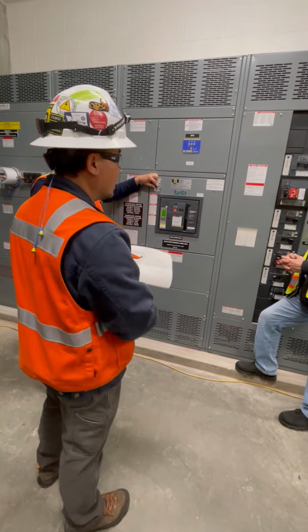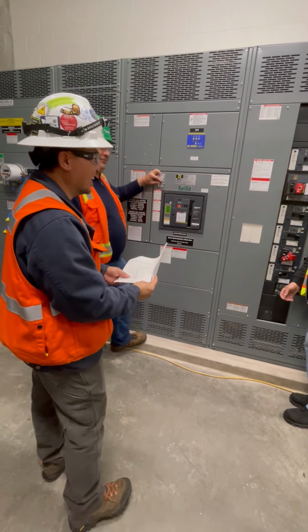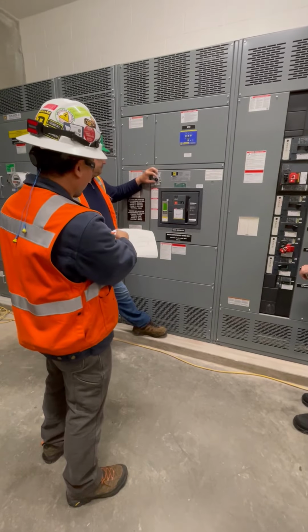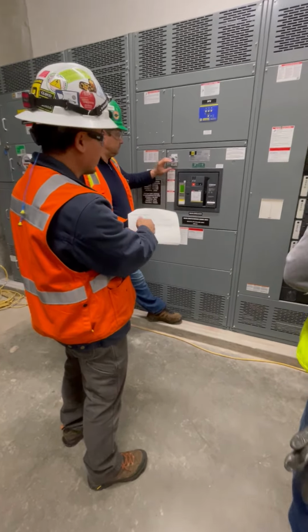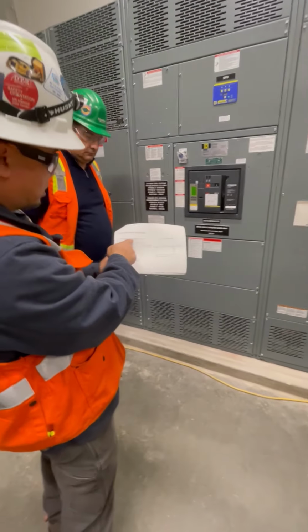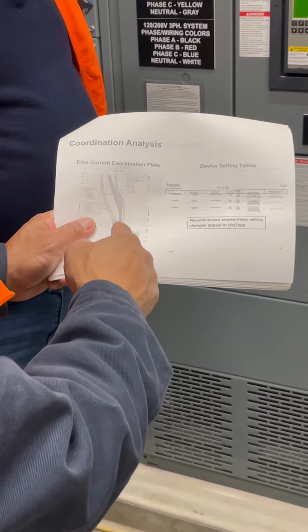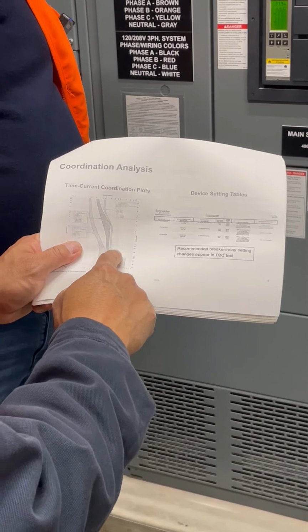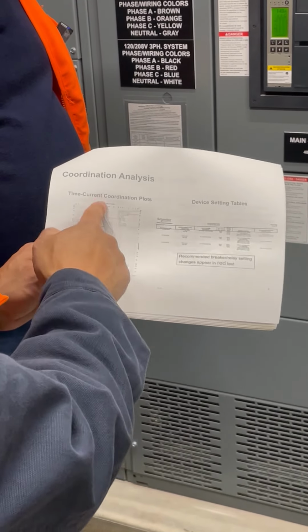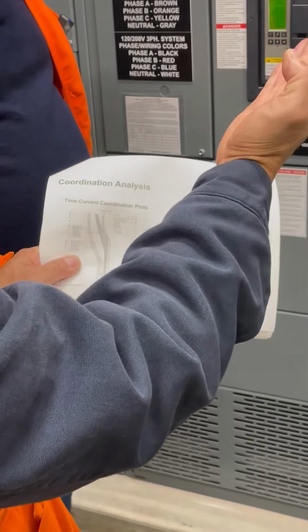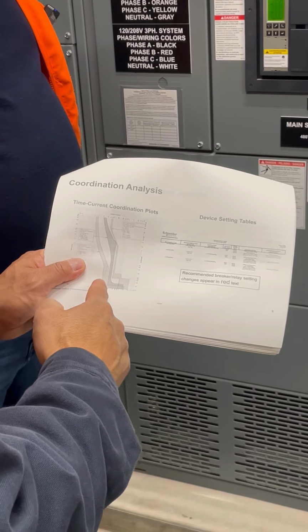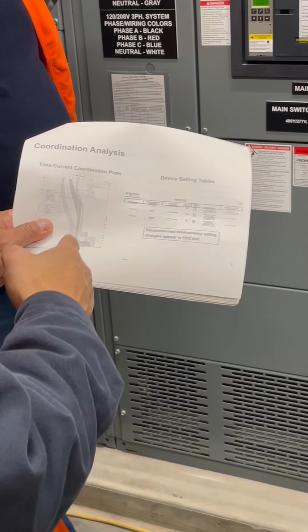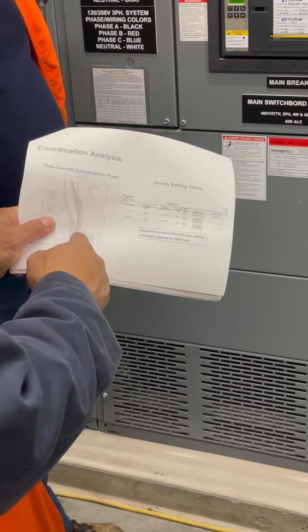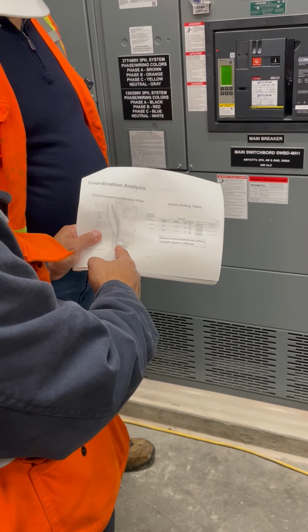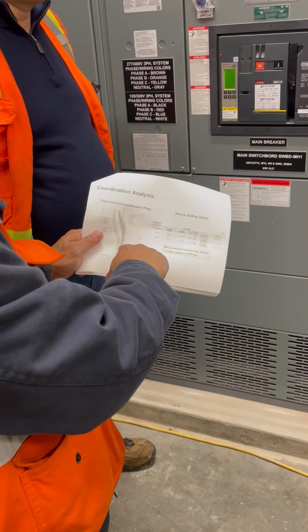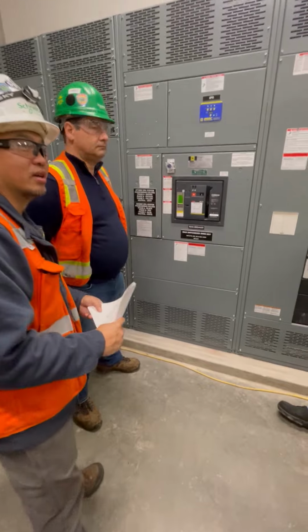Okay, that makes sense. So you have to work on something high. No, you're not supposed to. No. Do not. So here's what it does. Here's the characteristic, for example, of that breaker. In the off position, it's like this: here's your long time, here's your short time, and then here's your instantaneous. When it's in the off position, this is the way it's going to operate. If you turn it to the on position, this drops down to right here, to the left. So if you had a fault right here, now it's going to trip instantaneously, whereas if you left it in the normal position, a fault here would take longer to trip. So that's the intent of the ERMS switch.